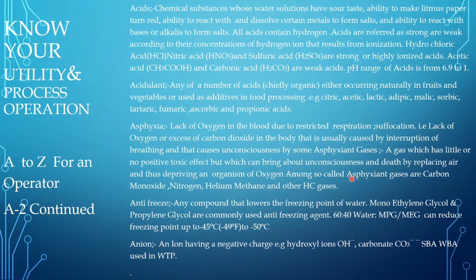In all industries, all the vessels, pipelines, or toxic materials will be purged using nitrogen after the stopping of the plant. After the purging, before vessel entry, confined space entry or any other job, we have to replace the nitrogen with pure air. We have to check the oxygen content and only then enter. If purging with air is not followed, then that nature is called asphyxiant nature, and that will lead to immediate death.